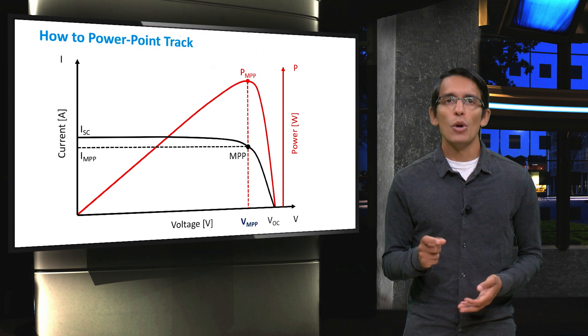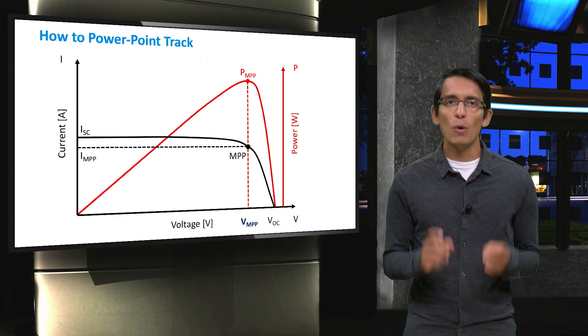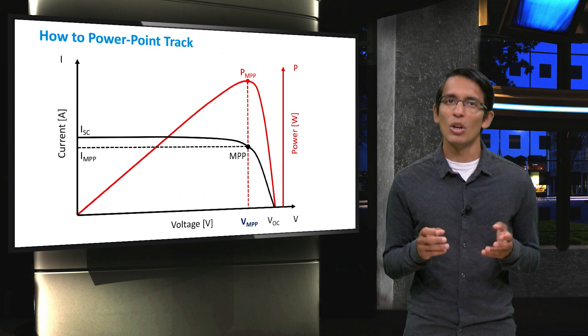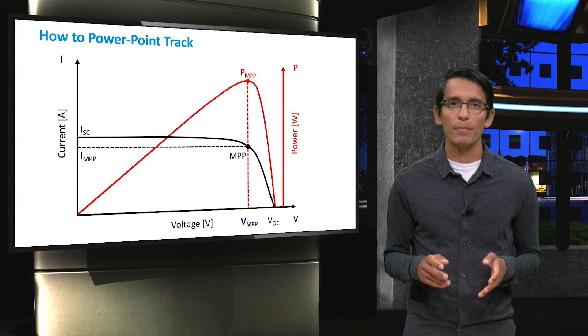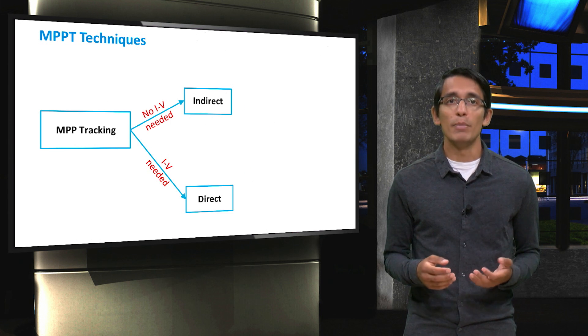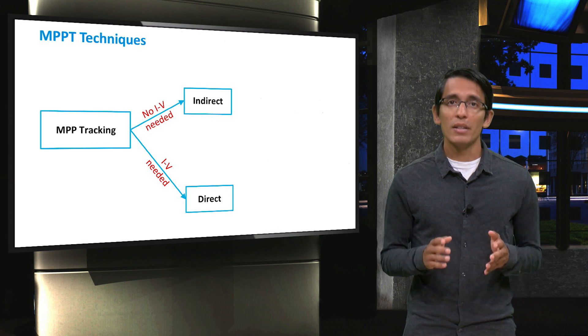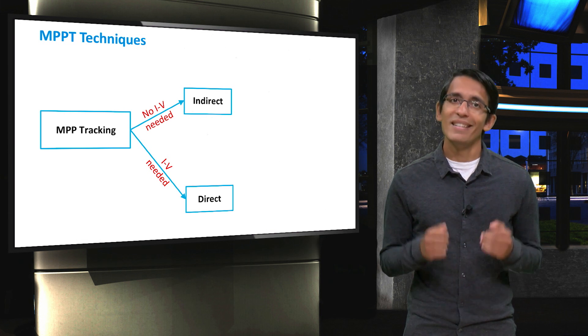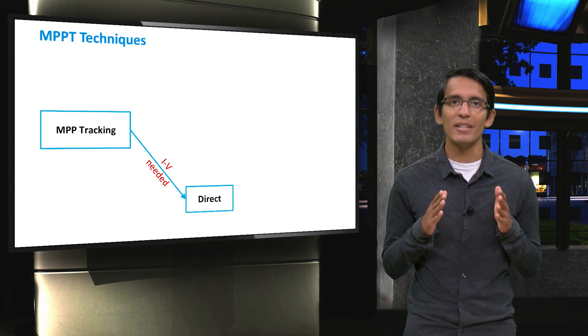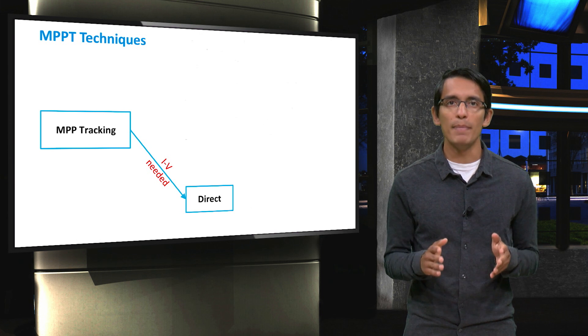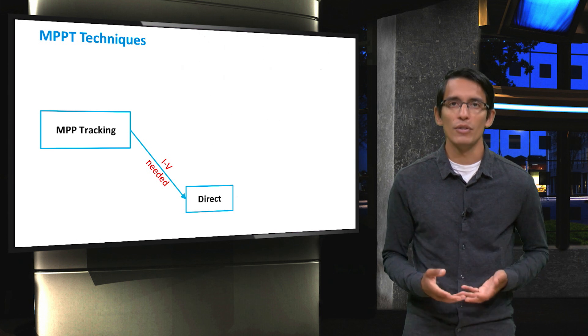By now, you should know that the goal of maximum power point tracking is to find the voltage at which a solar panel or array of solar panels delivers the most power. These techniques can either be indirect or direct. The incremental conductance technique is a direct technique, meaning that it directly scans the PV curve to find the MPP, rather than using some assumptions and calculations to do it.